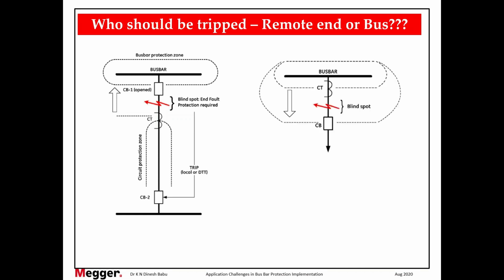Second, here also there is a fault between CT and breaker. You can see bus bar, CT, breaker, but the position is differentiated. CT and breaker are changed like this. So now let us understand the fundamentals. According to bus bar, this is an external fault because it's outside the CT. But according to the distance protection relay, this is a zone 1 fault, internal. Now who should trip? Let us see the step-by-step operation. First, distance protection will identify this fault in zone 1 and trip this circuit breaker. And it will also send a carrier signal to the remote end. Fine. Even after opening of this breaker, bus bar will start feeding this fault.